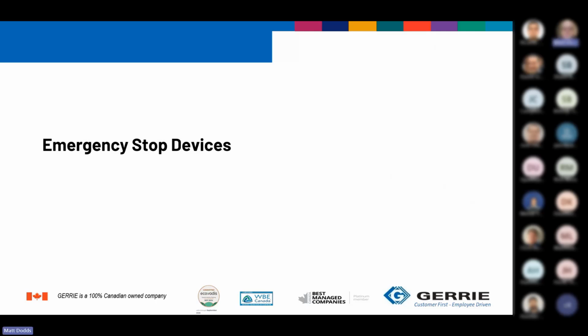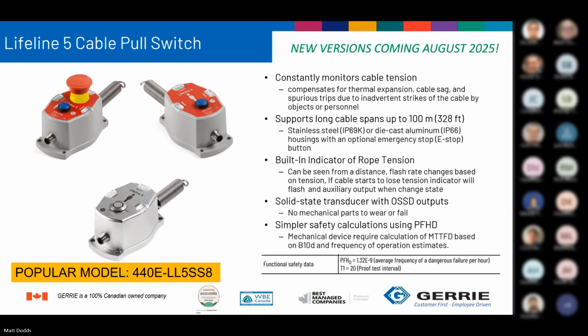E-stop devices. The Lifeline 5 cable pull switch, again, another one of my favorite products. These utilize a stainless wire rope or cable connected to a latching pull switch. When the rope is pulled in any direction along the length, the switch will be tripped. There are some new versions coming out in August with integrated guard link and a few other functions. But all I can say right now, look for the announcement on that.